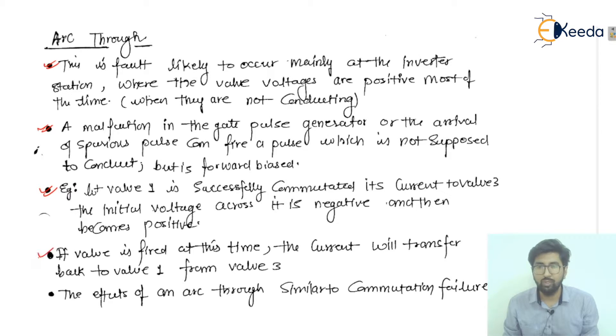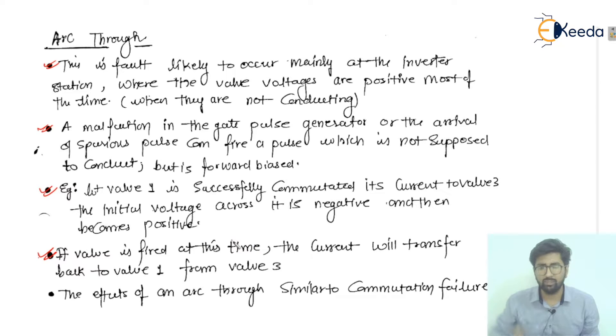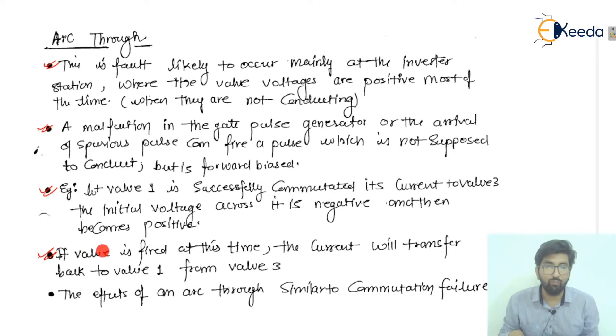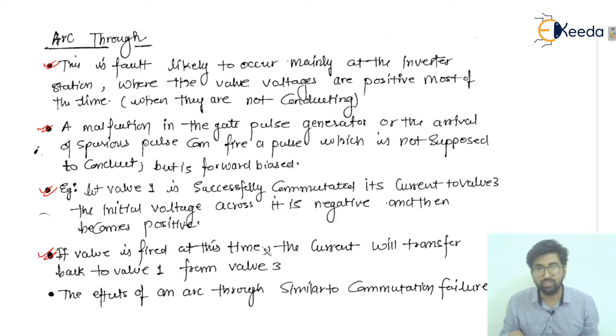If the valve is fired during this time — when commutation is occurring from valve 1 to valve 3 and the voltage is transitioning from negative to positive — then the current will transfer back to valve number 1 from valve number 3. That is actually commutation failure.